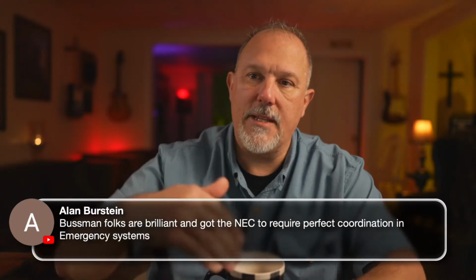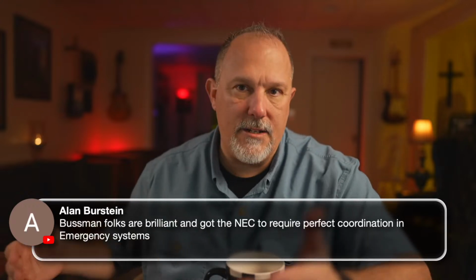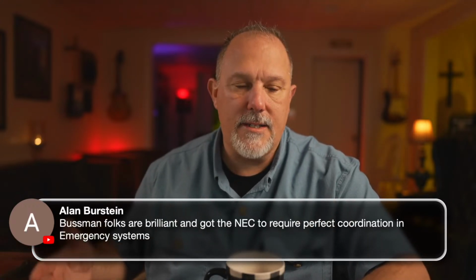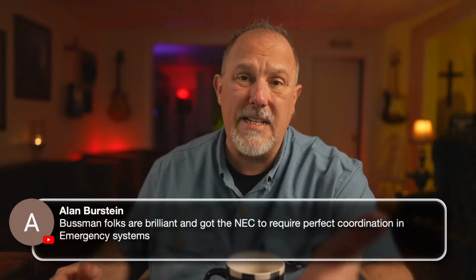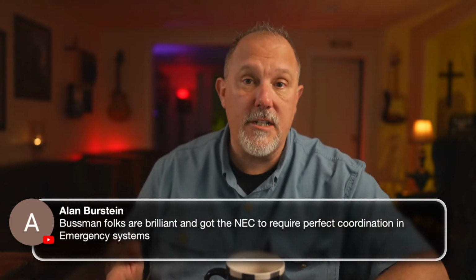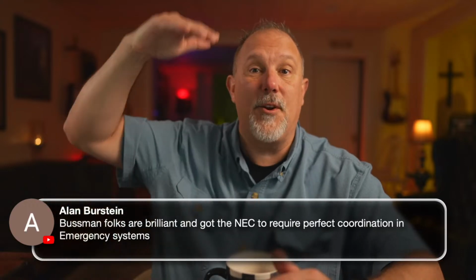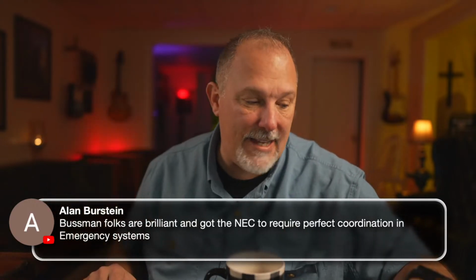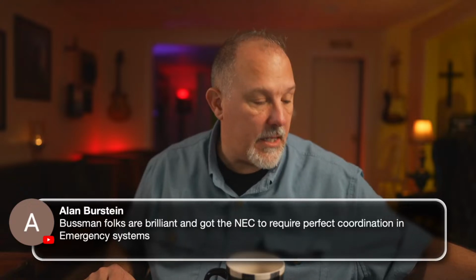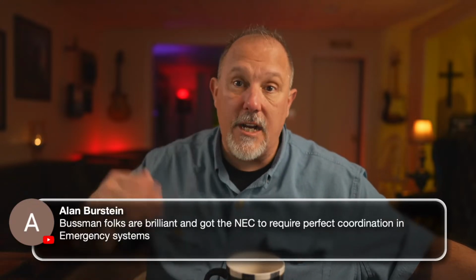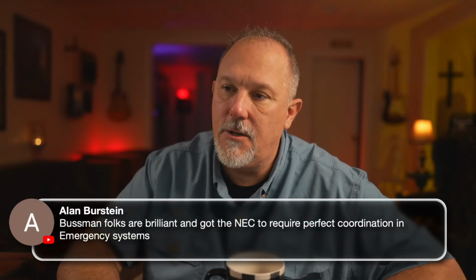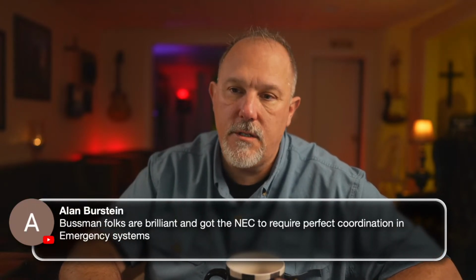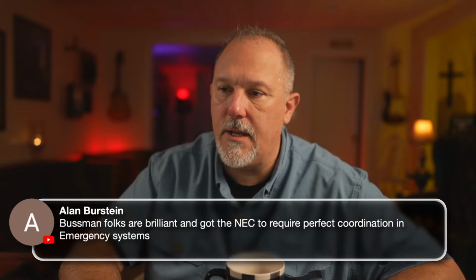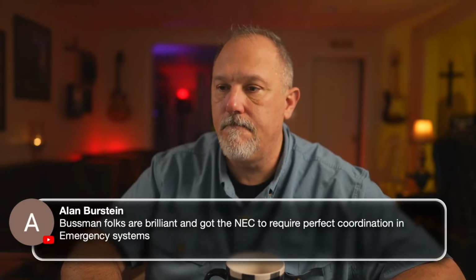And then as we talked about the incident energy, that's when Local 98, Jim Dollard, put the public input in to say, hey, let's put in 240.67 and 240.87, an arc reduction technology for these larger breakers, because that's where you're going to be adding these intentional delays. And we basically introduced an arc reduction requirement in the code. Remember, Alan, there were a lot of people playing in that sandbox, and there were different motivating factors.